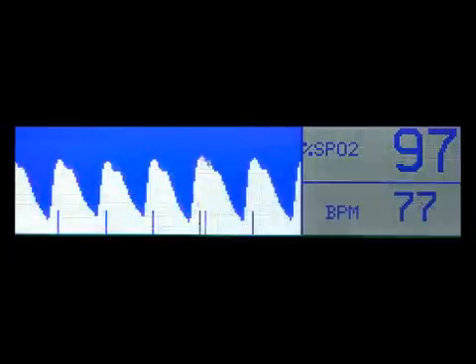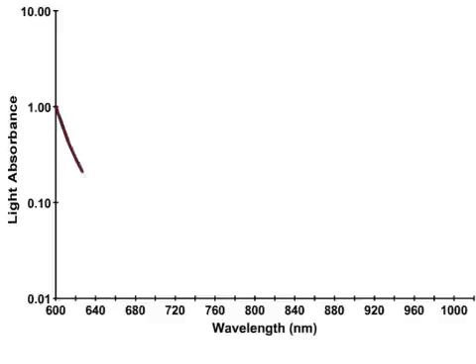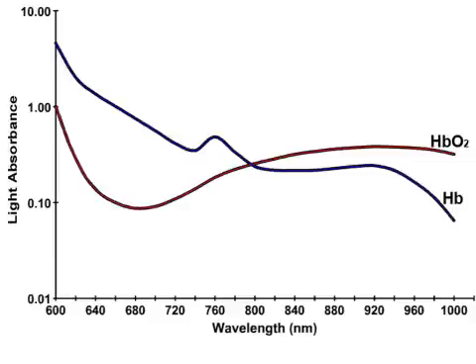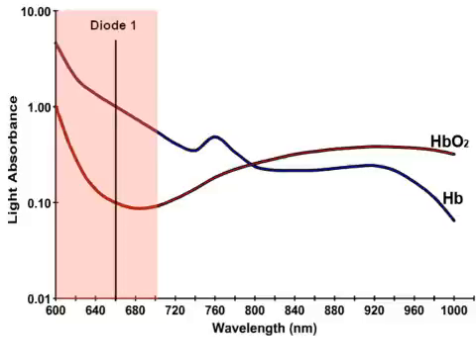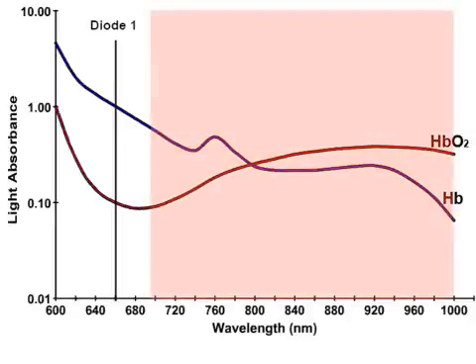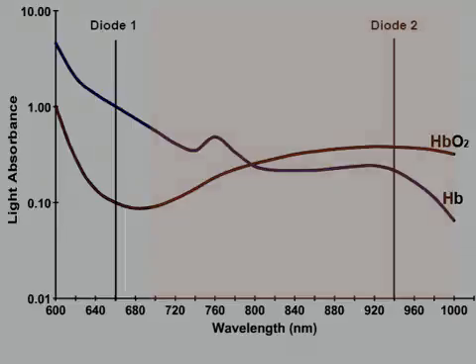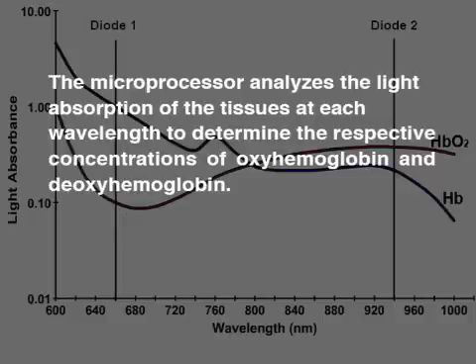The microprocessor calculates the percentage of oxyhemoglobin and displays the hemoglobin oxygen saturation in arterial blood, a waveform corresponding to the pulsatile flow in arterial vessels, and the heart rate. Pulse oximeters function on the principle that oxygenated and deoxygenated hemoglobin absorb red and infrared light differently. The light absorption of deoxyhemoglobin is greater at wavelengths of 600 to 800 nanometers, while the light absorption of oxyhemoglobin is greater at wavelengths of 800 to 1,000 nanometers. One light-emitting diode emits light in the red spectrum at a wavelength of 660 nanometers, at which the light absorption of deoxyhemoglobin is greater than that of oxyhemoglobin. The other diode emits light in the infrared spectrum at a wavelength of 940 nanometers, at which oxyhemoglobin absorbs more light than deoxyhemoglobin. The microprocessor analyzes the light absorption of the tissues at each wavelength to determine the respective concentrations of oxyhemoglobin and deoxyhemoglobin.